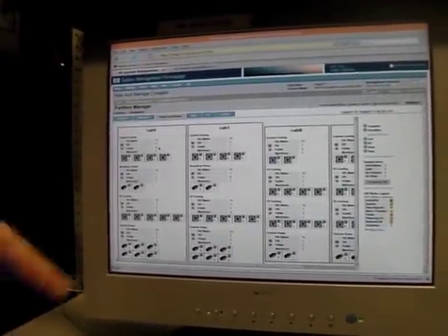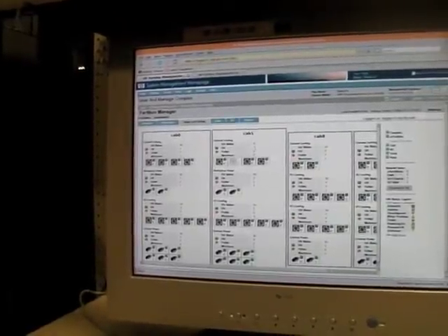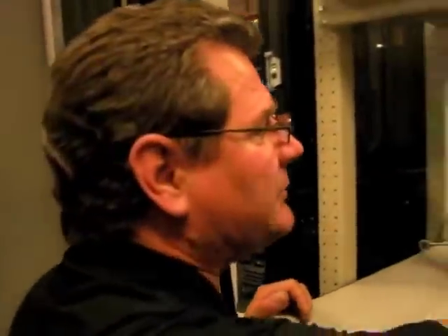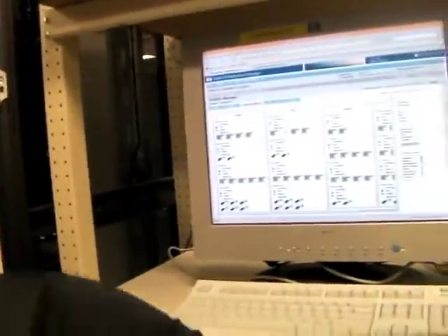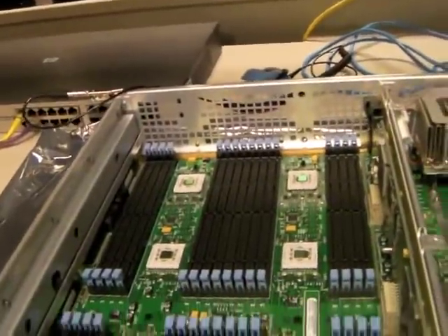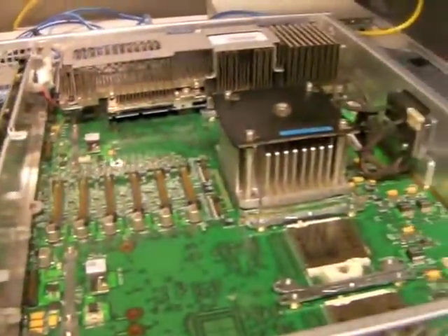So you might want to hit refresh. Did you actually do it? I did it. Okay. Sometimes it takes a little while. There you go. And so we have 3 okay and 1 that's actually been removed. It's not reporting failed, but it's not there. So it's being told, look, I'm not reporting one of the blowers. He actually took out 1, which should be the front right one. When he pushes that back in, we'll go back to getting 4 in that specific cabinet.